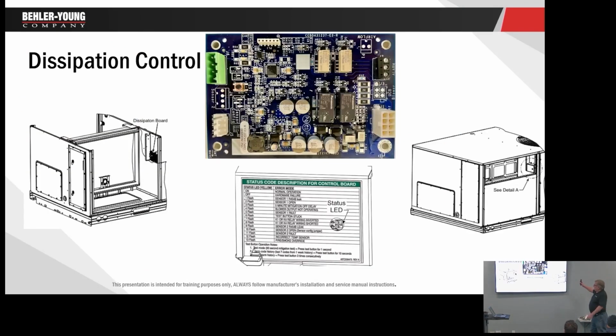So the sensor you can see mounted here at the base of the evaporator. Okay, and that's coming from the factory. And then you can see the dissipation board on the small chassis units is here, right inside the blower, the filter compartment to the right of the filter. You can see it here on the smaller units, there in the larger units. Okay, that sticker you see right there is the fault codes for this thing. It has a yellow light that's on constantly, means everything's good. Different flashes will tell you it's mitigated, or it has mitigated, the sensor's failed, or so on. So we'll look at that a little bit.